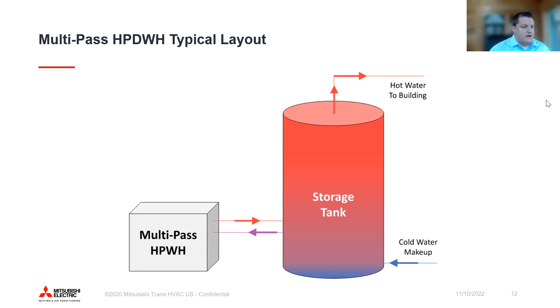And then the big difference is how you treat a single pass system. One of the real big keys to a single pass system, which most of the time is going to be CO2 based for refrigerant, is that you're getting really cold water back to the heat pump and giving it a really high delta T. Where our heat pump is going to be most efficient is where you get that cold 50-degree water back to the heat pump and give it 100-degree delta T leaving to your tanks. So with that, we do have to implement some different strategies on how we keep our storage in the system stratified.